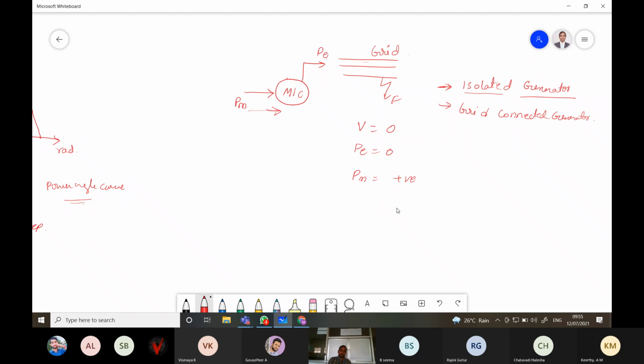Okay. So what happens for this? Your delta. Suppose this is the north and this is the south. So your rotor angle, this is south and this is north. So more pushing means your delta will be like this, because your mechanical input is more. So again, magnetic locking is not achieved here. Delta is more, so we need to clear this fault before this delta is more than 90 degrees.